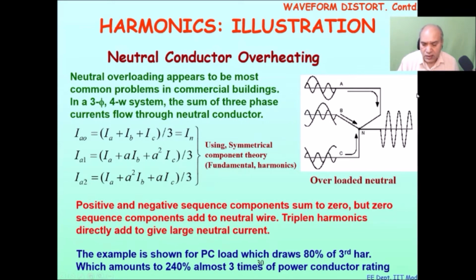And they create a huge magnitude in the current or voltage, mostly current here, because the current is being summed up, which becomes a problem for the design of the conductor rating, the neutral conductor rating. Sometimes the rating of this conductor goes to 240%, which is almost 3 times the power conductor rating. Okay, this is very interesting. Normally the neutral should be of 0 size because theoretically it should not carry any current. But because of practical situations, the return current, which is the sum of the 3-phase currents, has to be carried by it. And sometimes this current is more than the phase conductor rating itself.